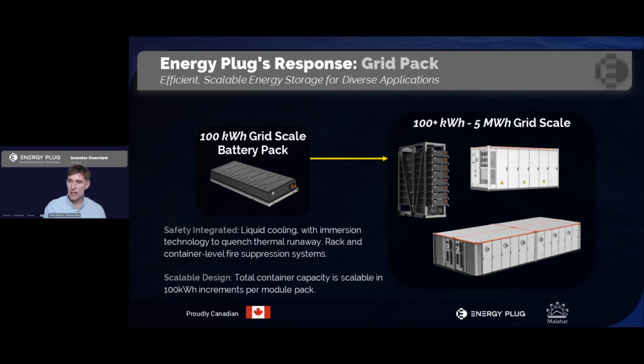One unique piece we can say is that the doors are only on one side and one edge. So at the bottom right there, you can see it allows for horizontal stacking to reduce a little bit of the ground footprint required. Of course, you could put some spacing between them for fire prevention if you would like. As far as thermal runaway goes, there is a three-level form of fire suppression in these systems. Within the module itself, it does a liquid immersion to quench any thermal runaway, and there are two other forms of dispersion within the rack and in the container itself to help deal with any fire concerns, which we know is an issue with LFP that we're seeing in the market. So we want to make sure that it's well addressed.